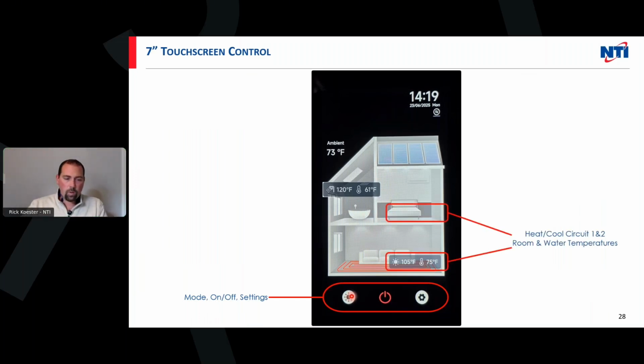In the rooms themselves, we are able to control some heat circuits here. What you're seeing in the bottom box is a buffer tank set point, as well as the actual temperature that's coming through the system. I was going to bring it up in the buffer tanks, but it doesn't hurt here either. If we have a system that's sized properly and we have a large mass, let's call it a radiant system, that is capable of achieving the volumes we need, so we're not short cycling the machine.